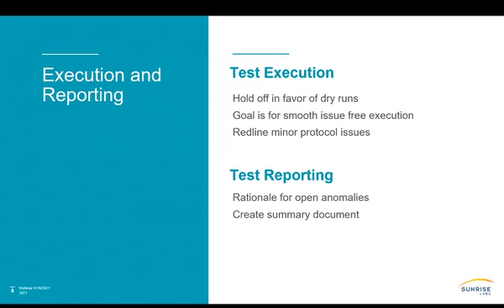And then regression testing. Regression testing analysis needs to be conducted when the device under test has changed, whether you have a new build of the software, something's been resolved, or there's a hardware change that's needed, packaging, labeling. It's also sometimes required to do regression testing based on changes in the protocol. I think it depends on how major the protocol deviation would be. But again, hold off as long as you can. Get extra dry runs in. Dry run is like the biggest piece of advice we can give with regard to test execution.